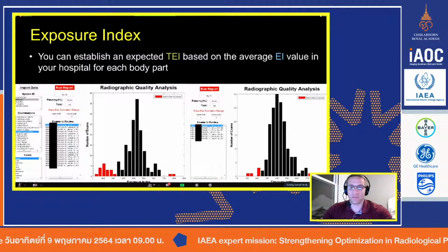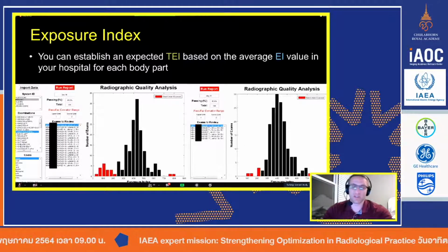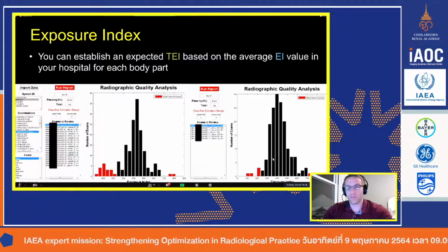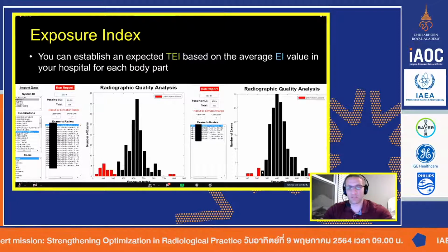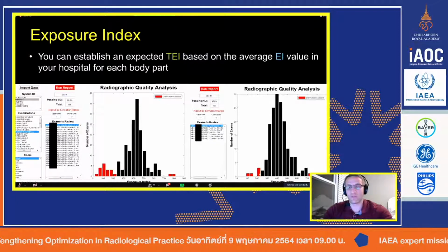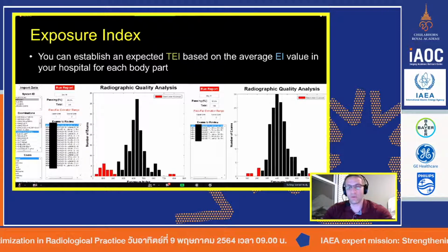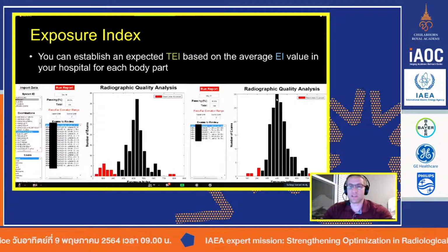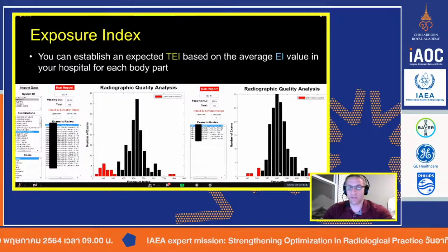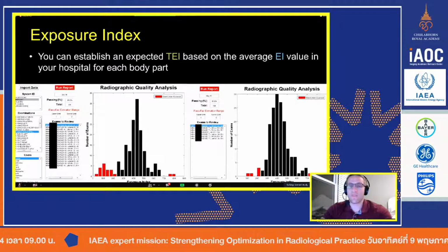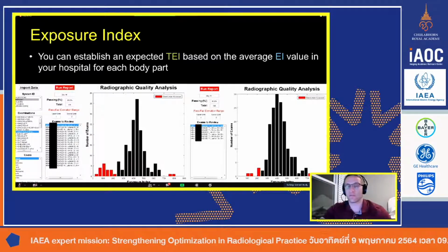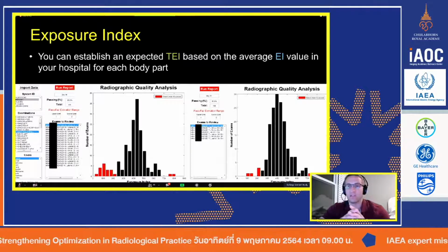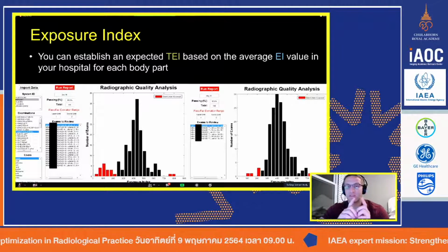And by May, as we worked with the technology to get everything a little bit better, you can see there was a lot better usage of the system, of this particular scanner. And there were very few patients that were under and very few that were overexposed based on my criteria. You can still see that the value in the center basically was the same. That is a very good candidate for target EI. So I could use the value that the vendor gave me.